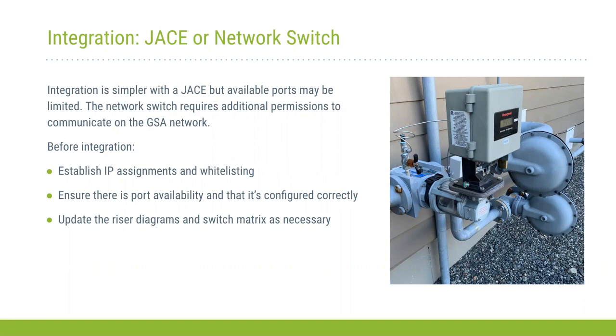As Sean talked about previously, we did a similar process there, but generally for the GSA project we decided to have a contractor install it. The contractor installed the cabling needed to mount the device, ran new conduit so it would fit, and provided a power source in the box it was mounted to, so it could easily be plugged in at a new location. They accomplished that in one day. With the system we had, Bill did the programming the second time and was able to copy and paste from one building to the next in the wire sheet. Next slide, please, Andrea.